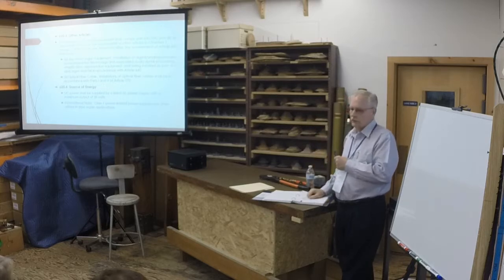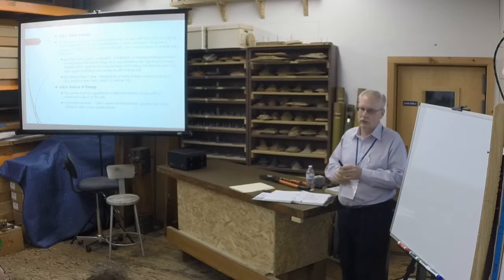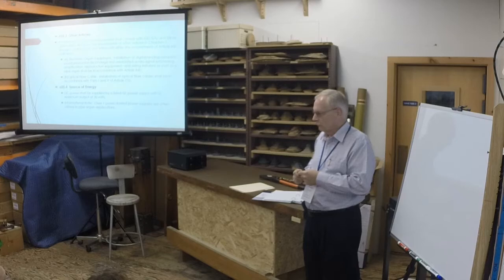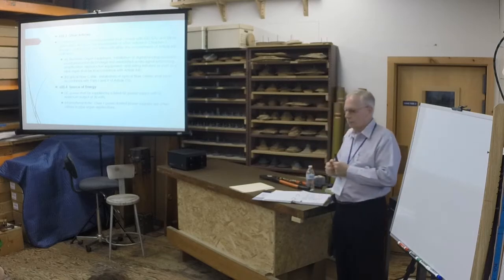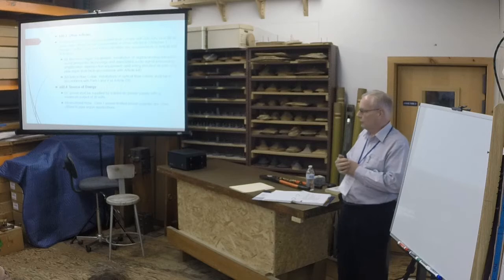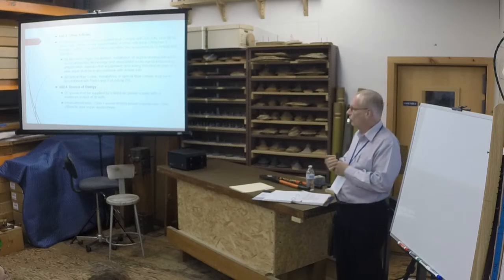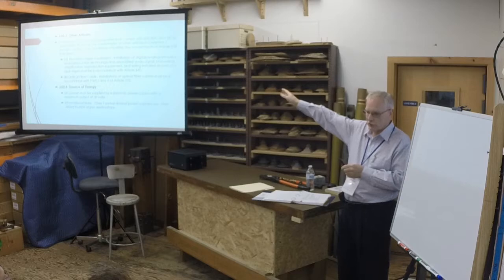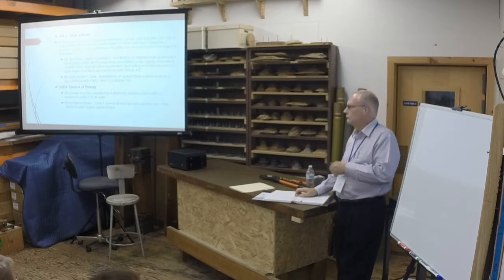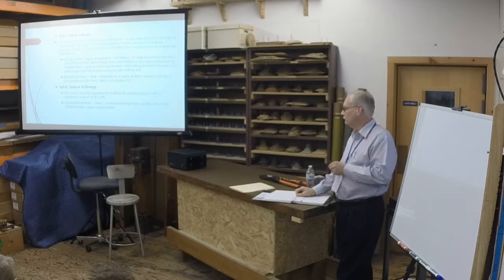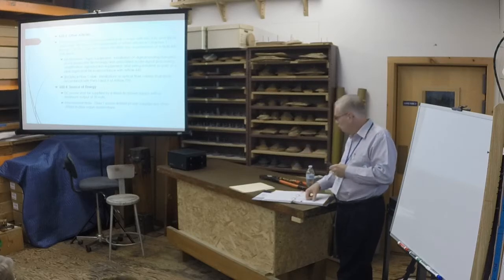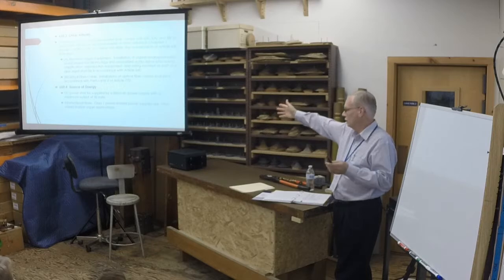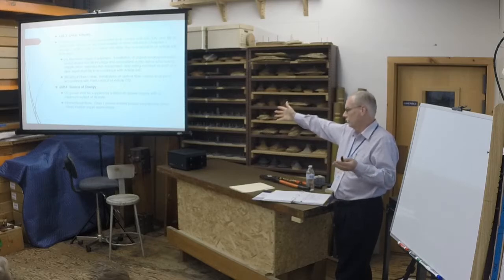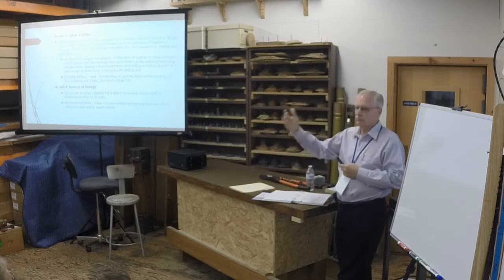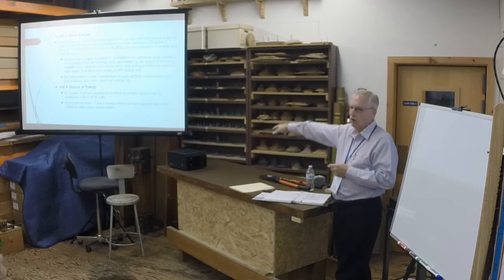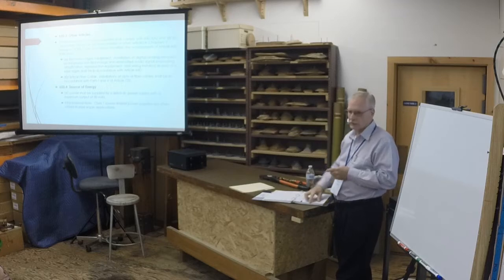So anybody out there thinking about doing what some builders have done over the years, putting 48 volts in a console to operate custom wound solenoid stop actions and so forth, that automatically takes you out of 650 of the code. As long as you're 30 volts and below, you're good. They've added this informational note: class 1 power limited supplies are often used by pipe organ specifications, which is just what was referred to this morning. These are all class 1 limited supplies.